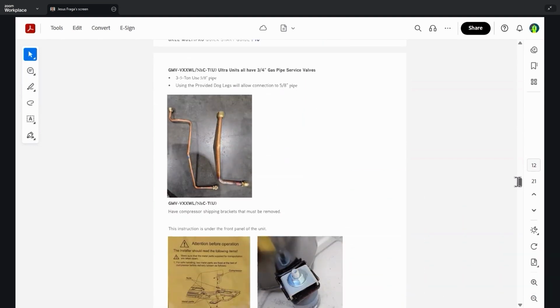Moving on, these additional pieces, or dog legs as we like to call them, will allow you connection of a 5/8 pipe. Pretty much it's an extension of the service valves from the compressor service valves to the outside of the unit. These will take you to the right-hand side, and it'll penetrate through the access hole and let you connect your line sets there. That way you're not having to use a ratchet bender or fittings to get up there to the flared connections. These dog legs let you connect at the service valves and come outside of the cabinet, so you're not having to do any ratchet bending or fittings. And each outdoor unit comes with these from the factory.